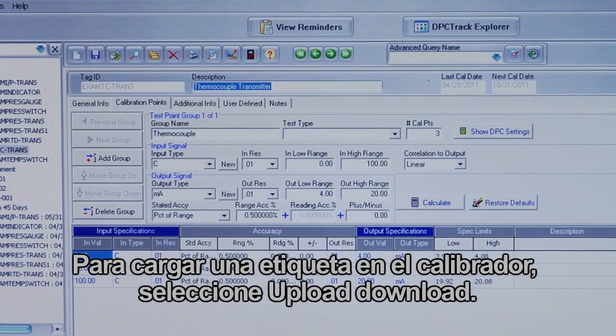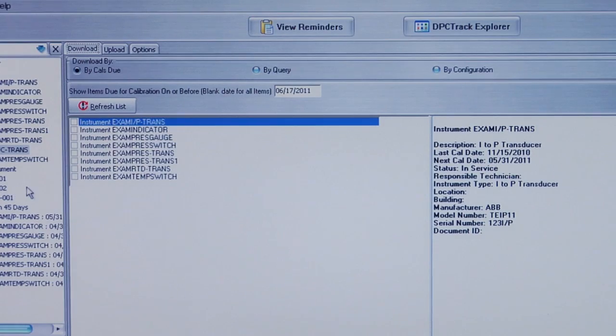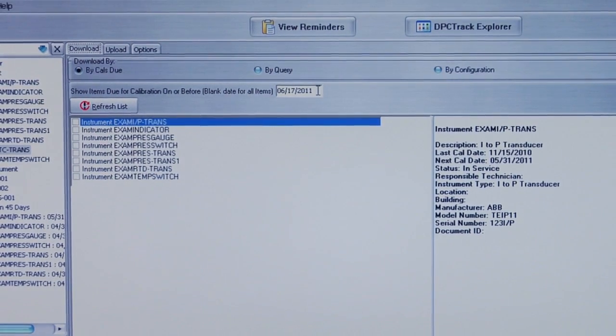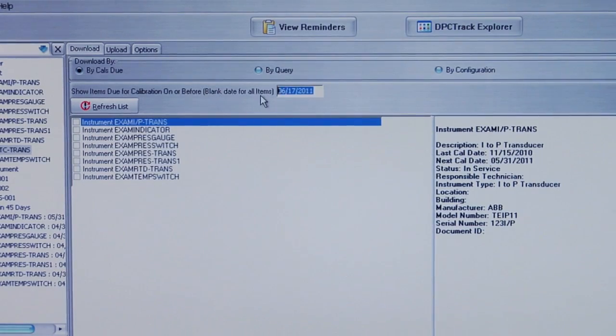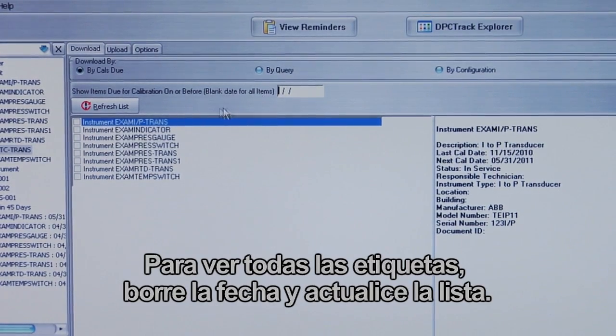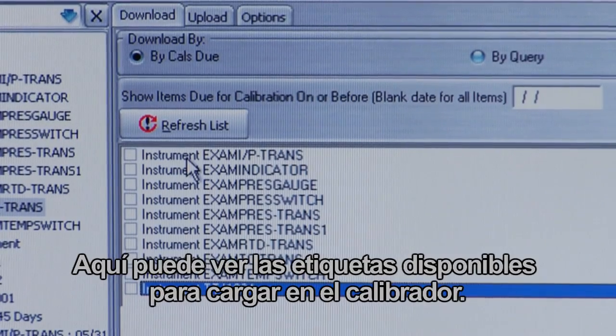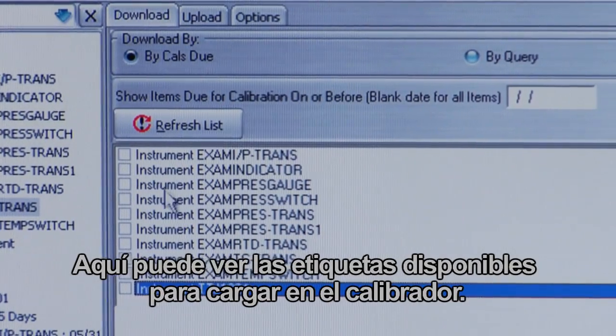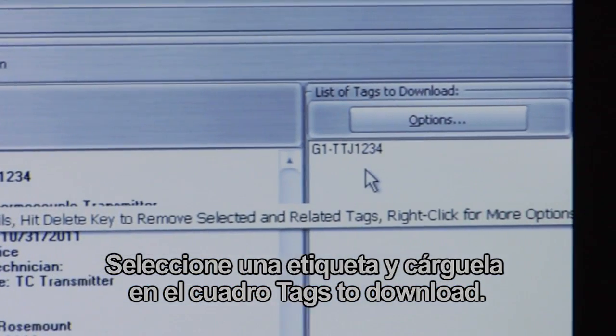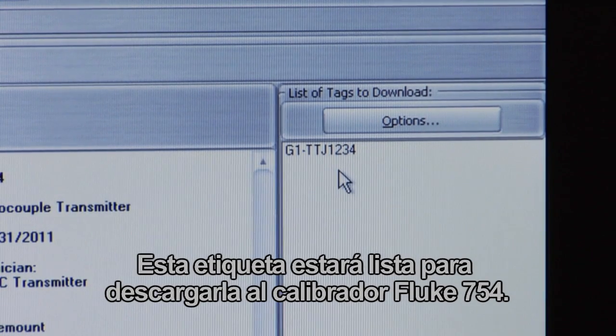To load a tag into the calibrator, select Upload/Download. Here you can see tags that are due or overdue by a certain date. To see all tags, clear out the date and refresh the list. Select a tag to load it into the tags to download box. This tag is now ready for download to the Fluke 754 calibrator.